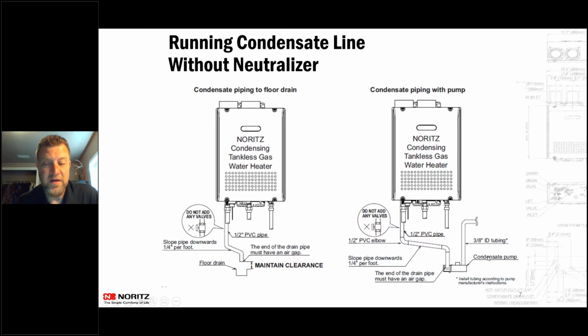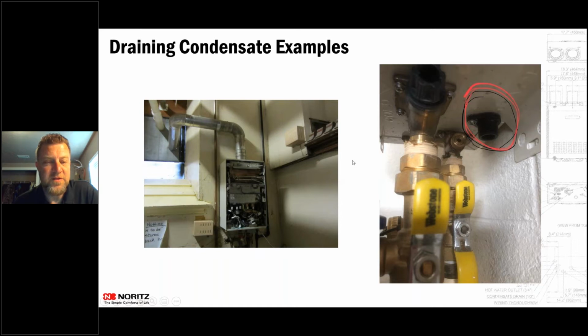You can run this into a condensate pump. If you are running that into a condensate pump, make sure that you're following the manufacturer's recommendations on how far that pipe going into the top is stuck down inside of that condensate pump, sending that out. We do have sensors inside of our unit, so if that condensate does back up, it'll throw an error code and let you know that it's backing up, which is something that we'll cover down the line. Not here in Utah, but in other states, I have seen that with condensate. Well, actually, I jumped ahead a little far.